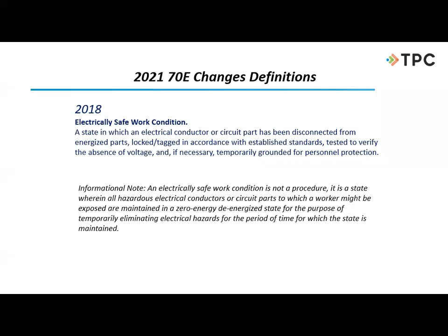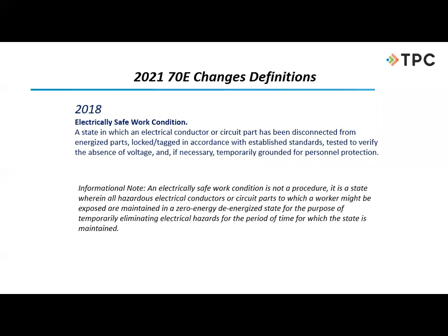Electrically safe work condition - in 2018, here we can see that definition, and in 2021 it really didn't change. So why is it in the PowerPoint? Because they gave us an informational note to make sure we understand this is the definition, not the procedure. It's a state in which everything has been disconnected, locked and tagged out per established standards, pretty much NFPA 70E, and then tested to verify the absence of voltage. All this is the definition, not the procedure or steps - we'd find those steps up in Article 120. They wanted to clarify that a little bit.